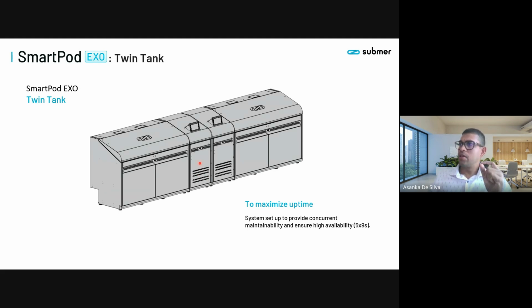And you could replace the failed CDU while the two tanks are running. So you can isolate the quick connect valves at the rear of the tank, remove the CDU, and then put the spare CDU in, reconnect the valves, and bring the second CDU online. So again, you establish redundant operation, right? This is a crucial feature for data centers, and again, it helps to ensure redundancy is maintained across the data hall and across the whole data center.